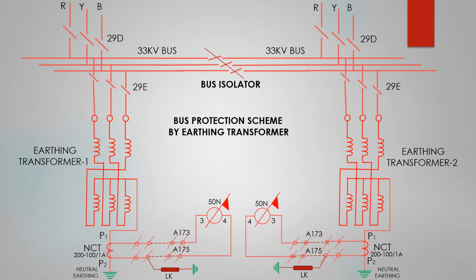When a bus fault or earth fault occurs at any of the bus sections, the total bus is required to be disconnected from the main supply. When transformers are running individually, only the section at which the earth fault occurs is to be disconnected. A switch ETS is used for this purpose, which has two modes, individual and both mode. When transformers run individually, switch ETS is kept at individual mode, and when they run in parallel, ETS is to be kept at both mode.